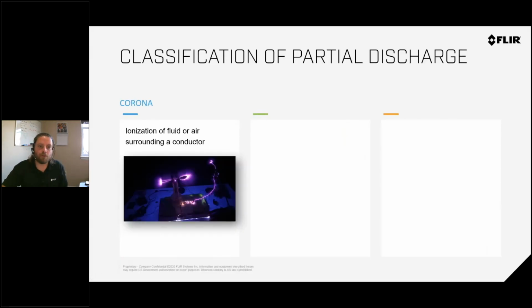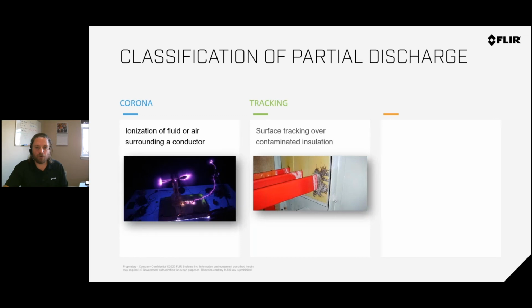So with partial discharge, there are 3 different classifications. We have corona, which is not the coronavirus, but ionization of fluid or air surrounding the conductor. This is the stuff when you're walking by power lines in your neighborhood or off the highway, and you hear that buzzing sound. That's corona, the ionization of the fluid in the air surrounding that conductor. Then tracking, where you could have surface tracking over contaminated insulation. If this thing gets contaminated, you're going to have this webbing effect, which is not good. It's going to damage your equipment.